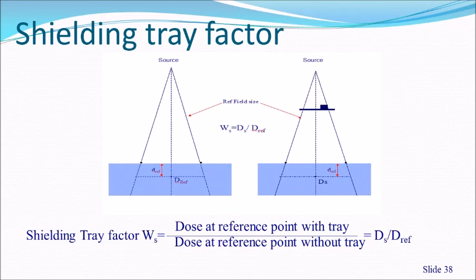Similarly, when a shielding tray is placed in the beam to hold shields, the acrylic tray itself attenuates the radiation by a few percent. The tray factor = dose at reference point with tray / dose at reference point without tray. This correction must be applied to the output whenever a shielding tray is used in the linear accelerator or telecobalt unit.